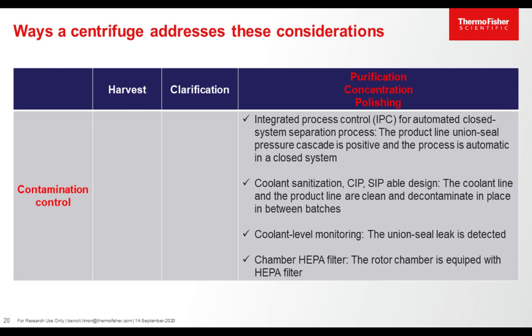When performing purification, concentration, and polishing steps to control contamination, please consider the following: use an integrated process control, which provides an automated closed system process and maintains pressure across the union-seal joints to reduce risk of contamination. Use a system capable of coolant sanitization as well as clean-in-place (CIP) and steam-in-place (SIP) to ensure sterile conditions. Use a system with coolant and lubricant fluid level monitoring to detect leaks and stop the process. Use a system equipped with a HEPA filter on the rotor chamber to prevent contaminants from escaping to the environment.